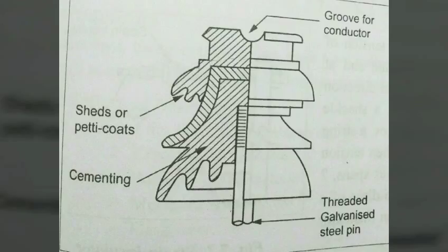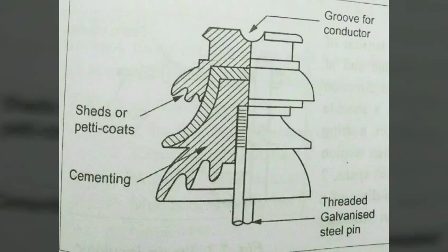Types of insulators. First, we will discuss pin type insulators. Pin type insulators are secured to the cross arm on the pole. The conductor is bounded into a groove on the top of the insulator. An adequate length of leakage path is obtained by providing the insulator with two or three petticoats or rain sheds.